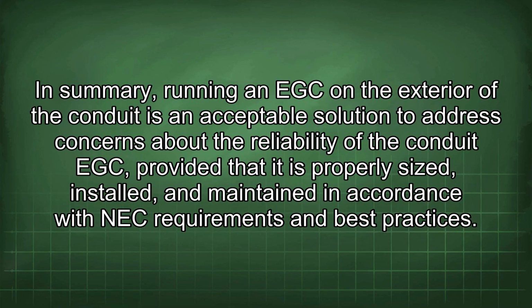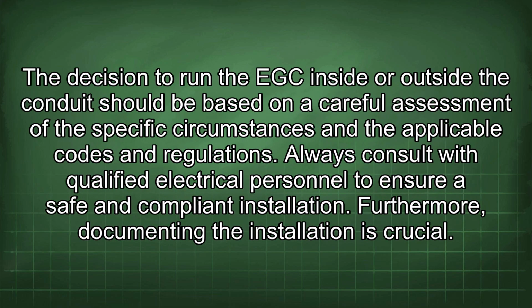In summary, running an EGC on the exterior of the conduit is an acceptable solution to address concerns about the reliability of the conduit EGC, provided that it is properly sized, installed, and maintained in accordance with NEC requirements and best practices. The decision to run the EGC inside or outside the conduit should be based on a careful assessment of the specific circumstances and the applicable codes and regulations. Always consult with qualified electrical personnel to ensure a safe and compliant installation.